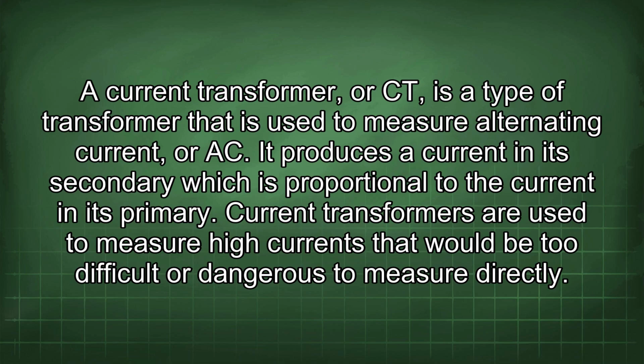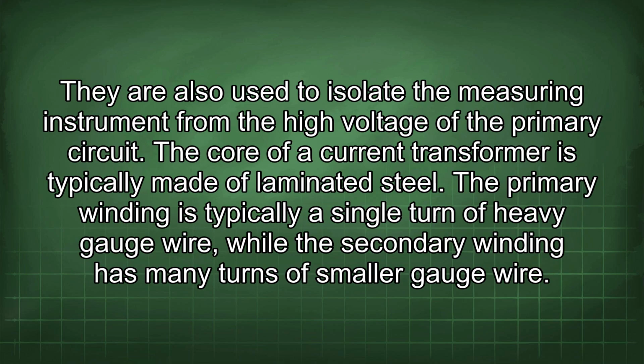A current transformer, or CT, is a type of transformer that is used to measure alternating current, or AC. It produces a current in its secondary which is proportional to the current in its primary. Current transformers are used to measure high currents that would be too difficult or dangerous to measure directly. They are also used to isolate the measuring instrument from the high voltage of the primary circuit.